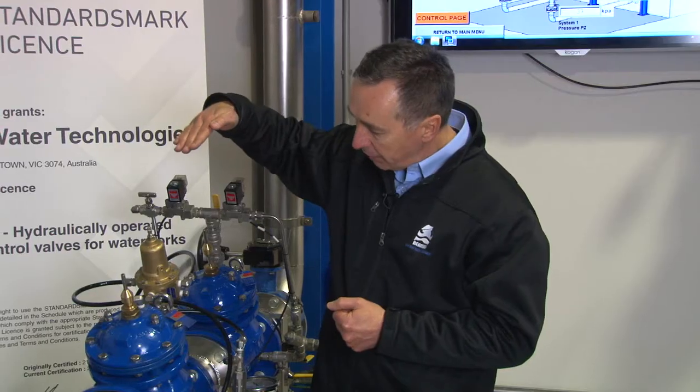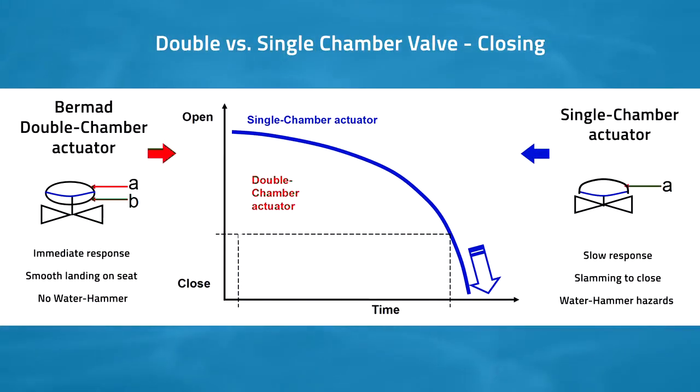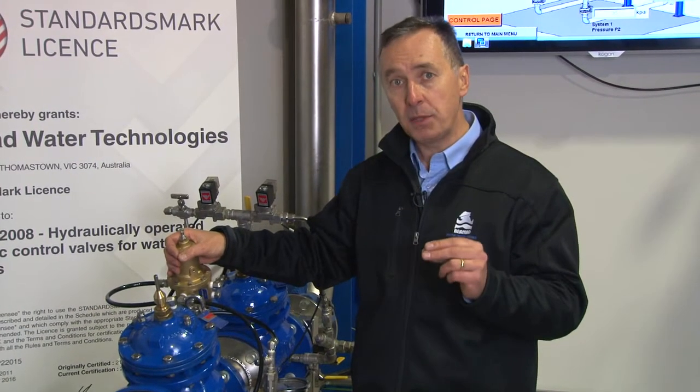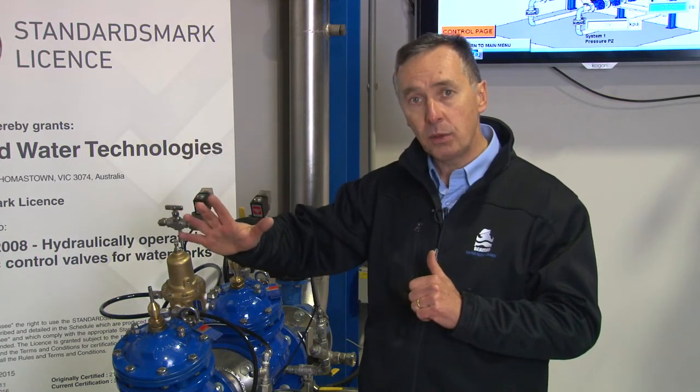The double chambered valve closes at a linear rate — much faster than a typical single chambered valve — but importantly, when it reaches the last 20% of its stroke it tends to slow down. The net effect is positive, very high, reliable closing that is completely surge-free. Surges are typically generated in the last 20% of closing, and the Bermad valve closes linearly and slows in that final 20%.